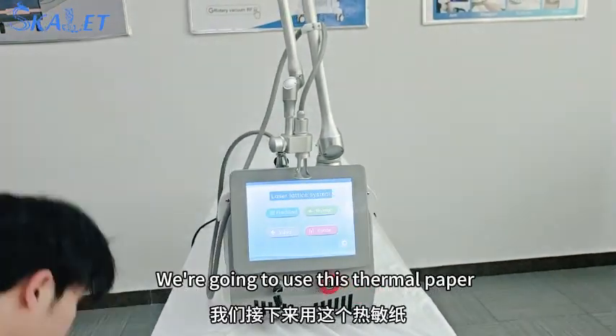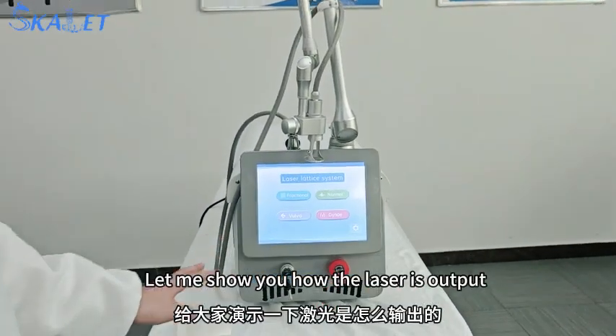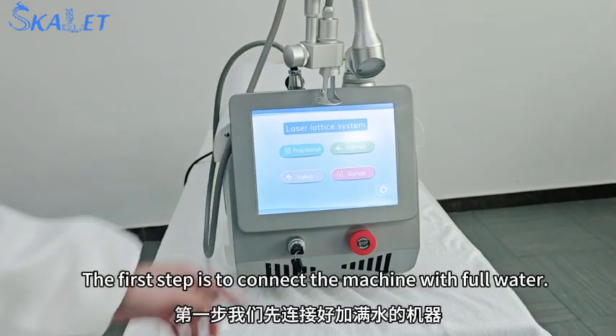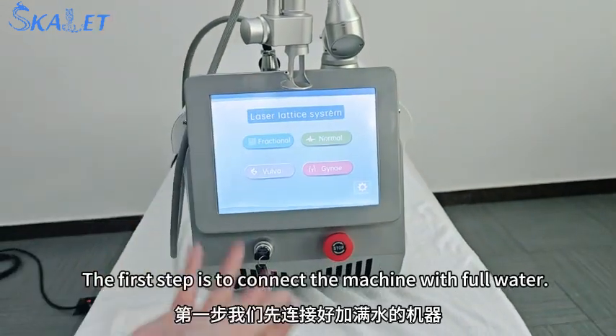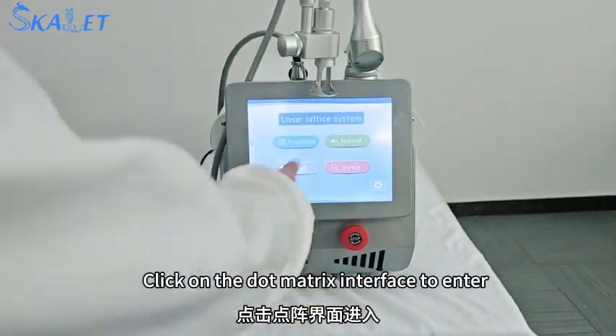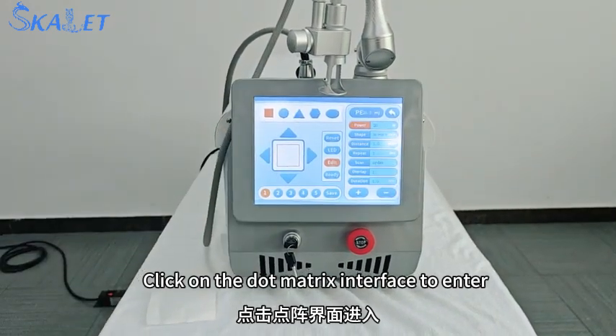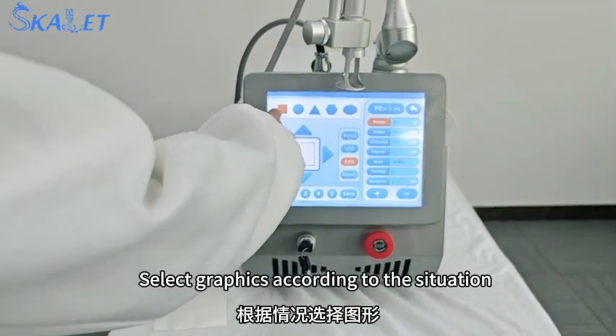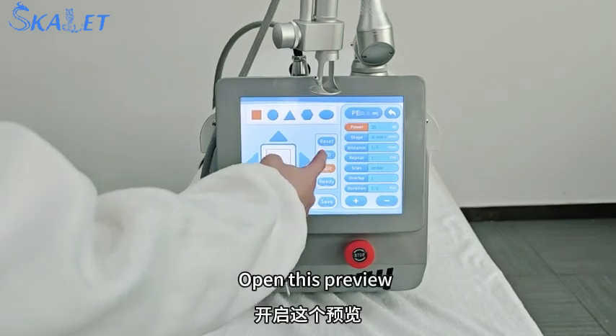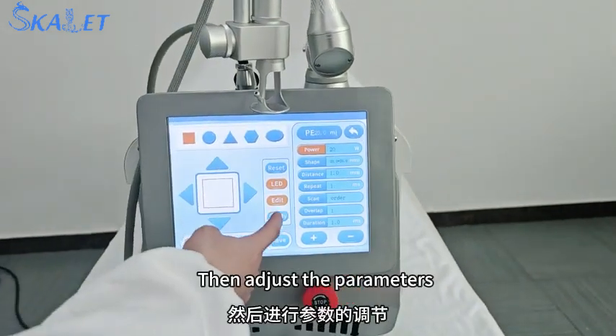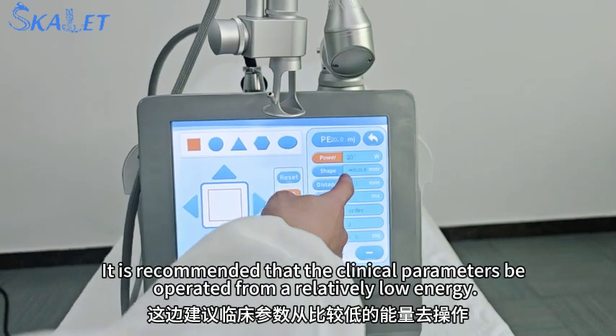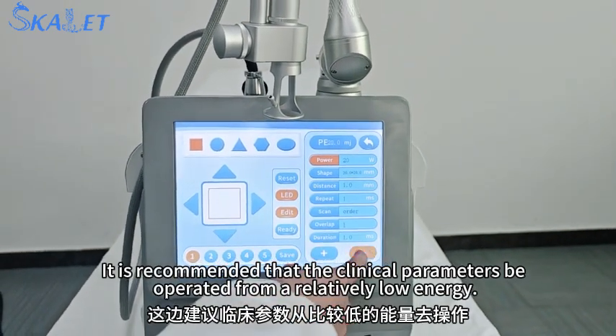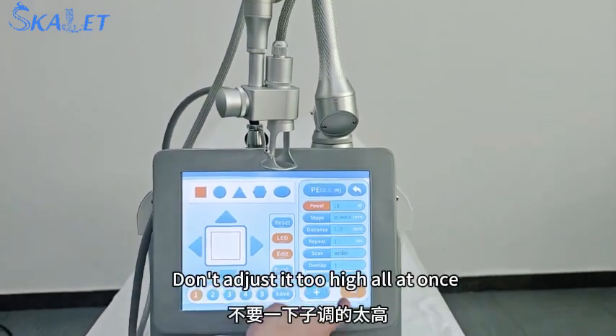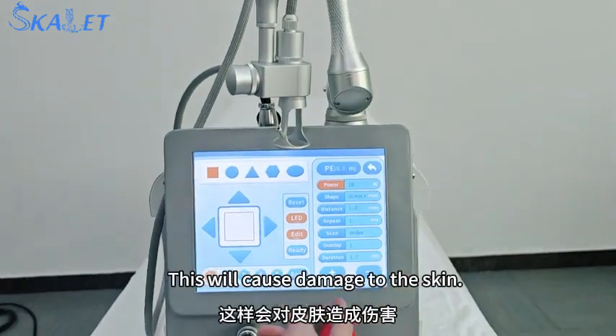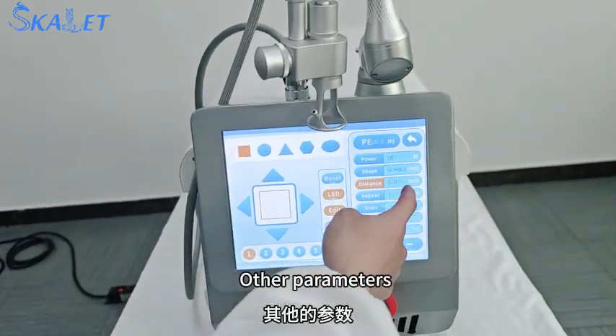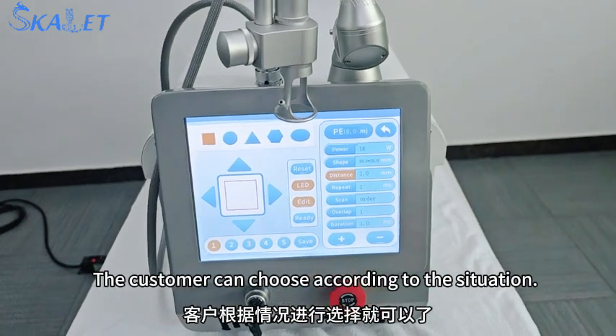We're going to use this thermal paper. Let me show you how the laser is output. The first step is to connect the machine with full water. Click on the dot matrix interface to enter. Select graphics according to the situation. Open this preview. Then adjust the parameters. It is recommended that the clinical parameters be operated from a relatively low energy. Don't adjust it too high all at once. This will cause damage to the skin. Other parameters, the customer can choose according to the situation.